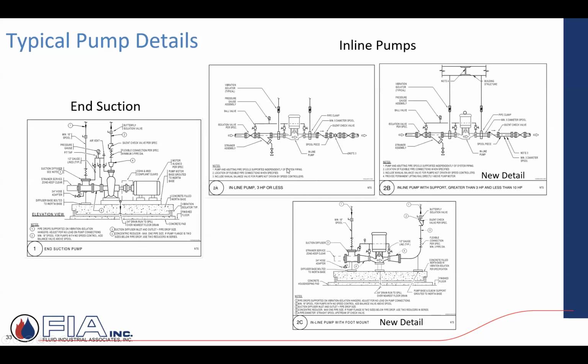Well, it really gets into how big the pump is, how big the horsepower is, what the flow rate is, because it will impact how we are supporting it. We're never really attaching to the pump itself, but we want to support the piping on either side, suction and discharge. And then how rugged or robust that support is as the horsepower gets larger. In this case, they're talking up to over 3 horse and maybe somewhere around 10 horsepower.